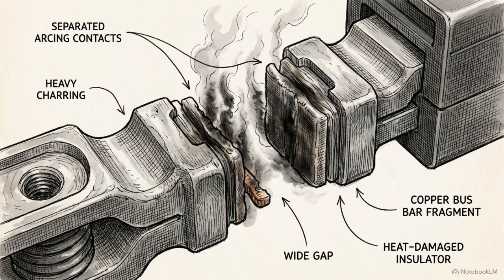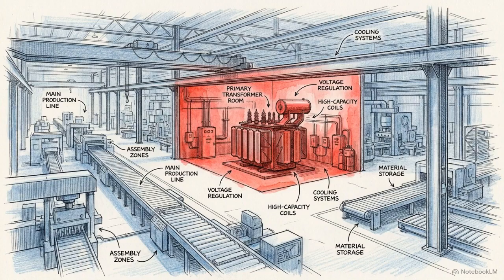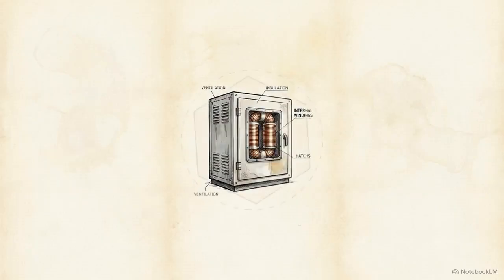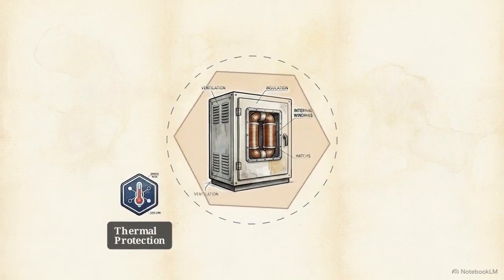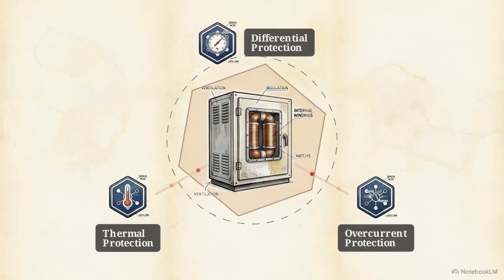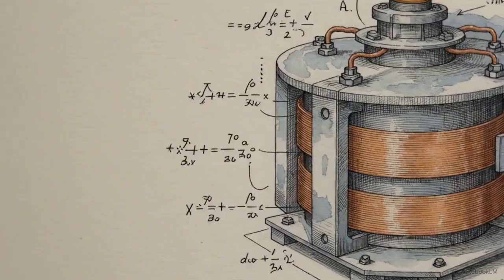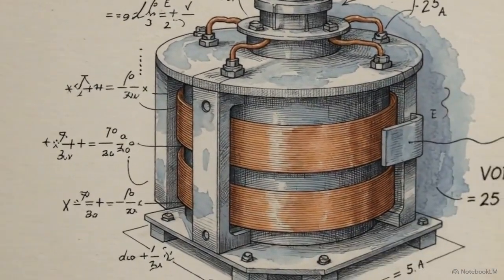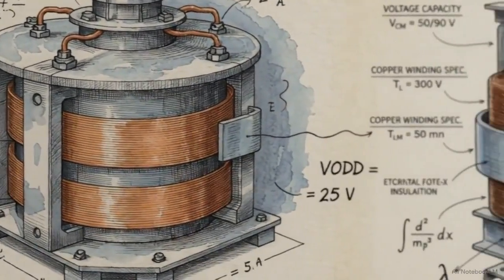Differential protection provides the fastest, most decisive isolation for internal faults. It cuts the power long before the extreme thermal and mechanical stress can cascade through the rest of the facility. We have now successfully implemented a complete 3-part protocol: thermal, overcurrent, and differential protection. What started as a highly vulnerable system is now a secured, robust asset.